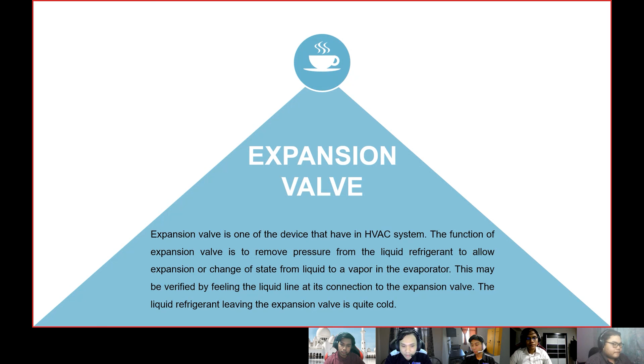How does the expansion valve work? To understand how the expansion valve works, we must understand the direct relationship between temperature and pressure. When the refrigerant pressure increases, the temperature also increases. The relationship between pressure and temperature also works in the opposite direction: by a reduction in the pressure of the refrigerant. In simple terms, as the refrigerant's pressure gets reduced, it can also be effectively cooled off.